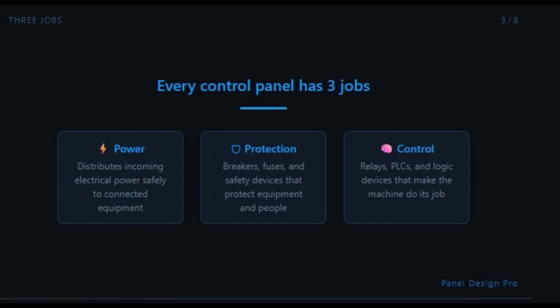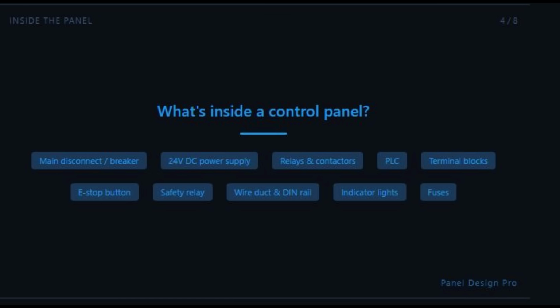Every control panel has three basic jobs. Number one, power distribution: it takes incoming electrical power and distributes it safely to the equipment it controls. Number two, protection: it contains circuit breakers, fuses, and safety devices that protect both the equipment and the people working around it. Number three, control: it contains the logic, whether that's relays, PLCs, or other control devices, that makes the machine do what it's supposed to do. Let's look at what's actually inside a typical industrial control panel.